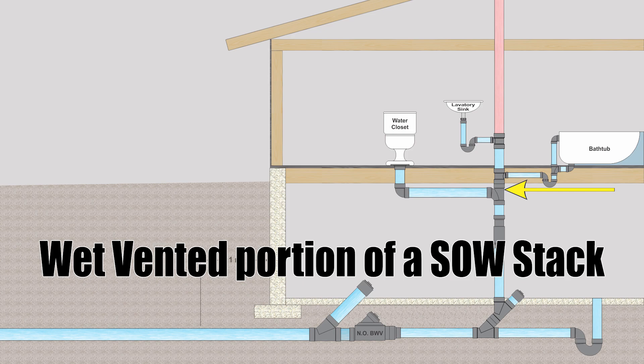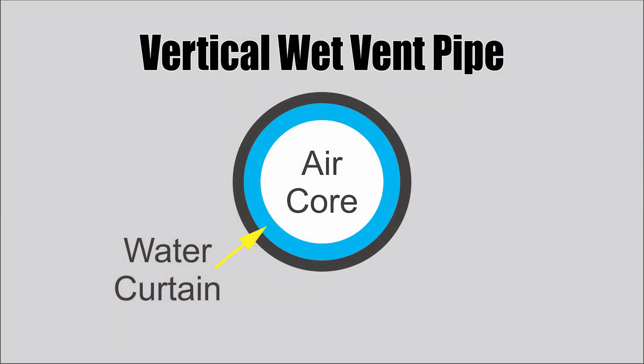When our wet vent is going down a vertical pipe there's a slightly different dynamic happening. The water itself swirls down and clings to the inside wall of the pipe, leaving an air core right in the middle. So the pipe will only be about half full, but the center of that pipe will be the venting portion.